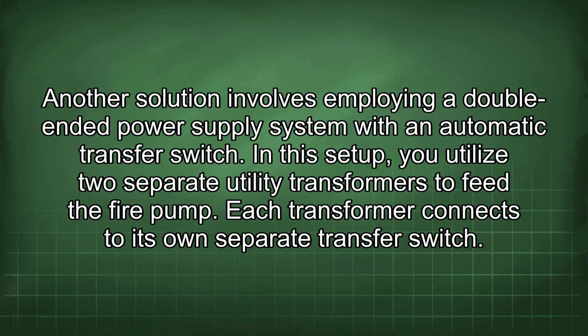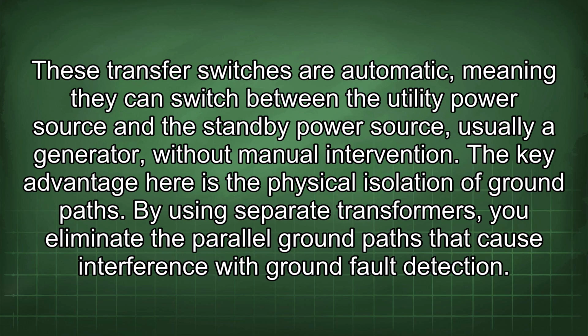Another solution involves employing a double-ended power supply system with an automatic transfer switch. In this setup, you utilize two separate utility transformers to feed the fire pump. Each transformer connects to its own separate transfer switch. These transfer switches are automatic, meaning they can switch between the utility power source and the standby power source, usually a generator, without manual intervention.